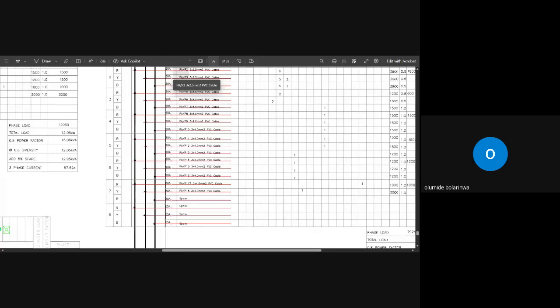You calculate that one. Now you go to your cooker unit, because your cooker unit is 45 amps and you can't use 2.5 cable. Sometimes you can manage with a smaller cable, but me, I usually use 6 cable. But based on what this side is doing, we are being told that we'll be using 4 cable. So it is 9.5 meters times 3 times the number of cooker units you have in that area. You have already sorted out your 1.5, 2.5, 4 and 6 cable.